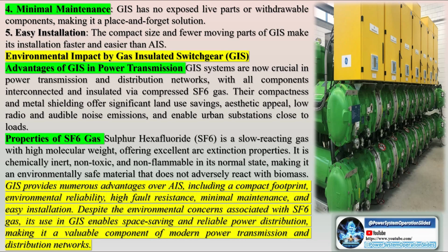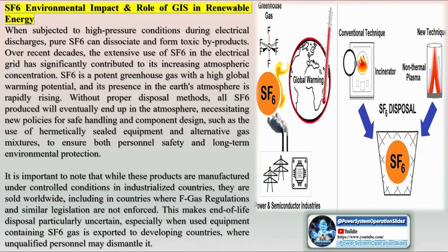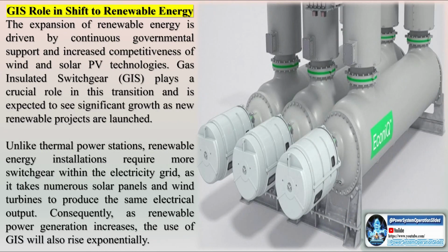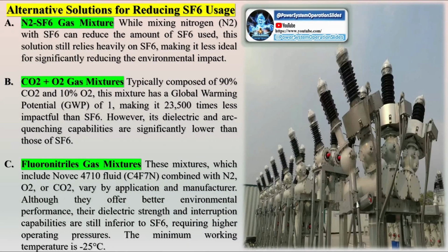While gas-insulated switchgear has numerous advantages, it is essential to be aware of its limitations to make an informed decision between GIS and other types of switchgear, such as air or oil-insulated variants. The main drawbacks include high cost. One of the major disadvantages of GIS is its high initial cost compared to other types of switchgear. However, the long-term benefits, such as minimal maintenance, can offset the initial investment. Longer outages: if GIS experiences an internal fault, the sealed nature of the equipment can lead to longer repair times.